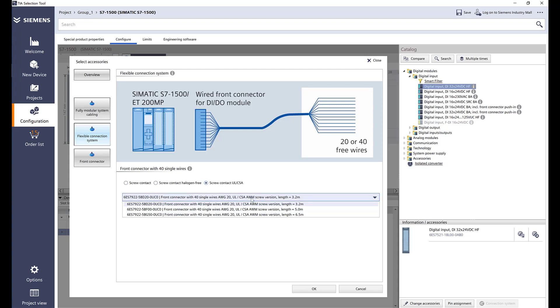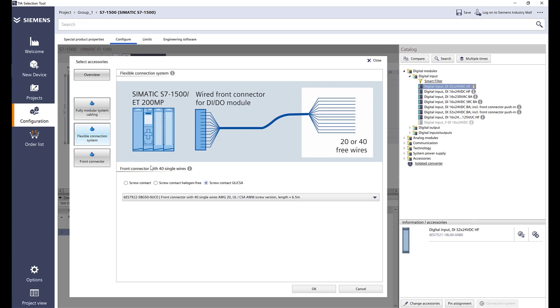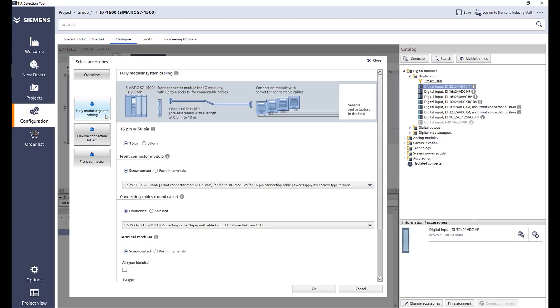I'll select the UL version. Here are different lengths that you can select up to 6.5 meters. Or we can go to this fully modular cabling system. What that means is there is a connector, then there is a pre-assembled ribbon cable style cable that goes from the connector on the PLC to the IO modules.